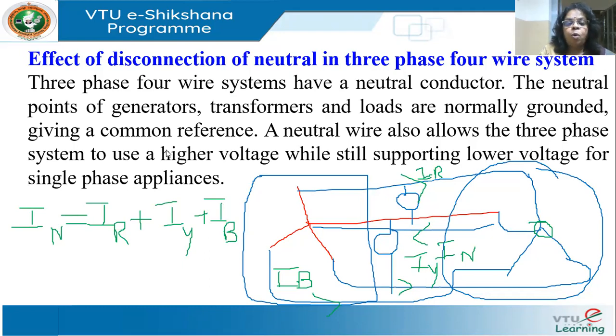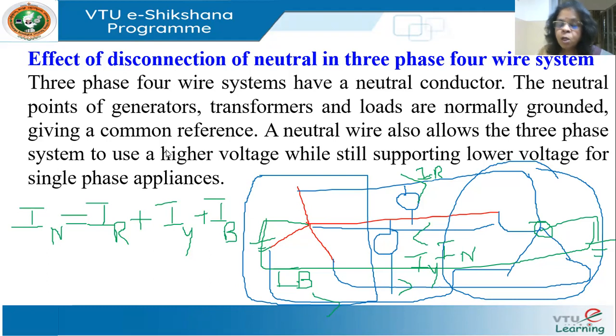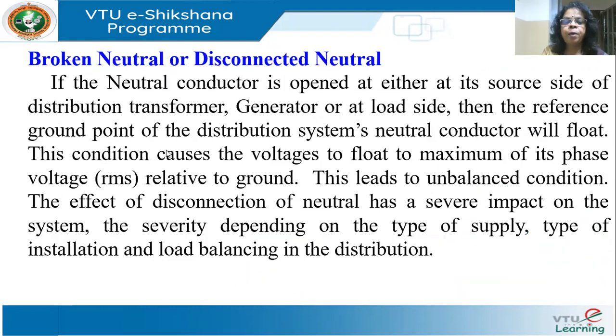A neutral wire allows the three-phase system to use a higher voltage while still supporting lower voltage for single-phase appliances. Between line and neutral you get the phase voltage — 1/√3 of the line voltage — so you can get a lower voltage with the same system. That's the advantage of a three-phase four-wire system.